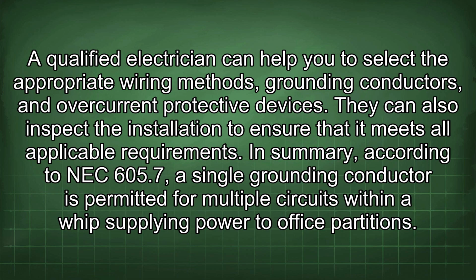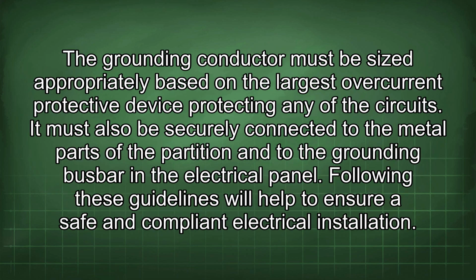In summary, according to NEC 605.7, a single grounding conductor is permitted for multiple circuits within a whip supplying power to office partitions. The grounding conductor must be sized appropriately based on the largest overcurrent protective device protecting any of the circuits. It must also be securely connected to the metal parts of the partition and to the grounding busbar in the electrical panel.